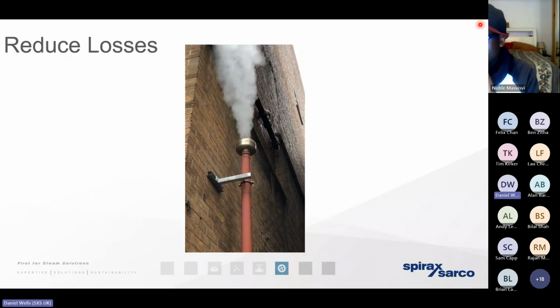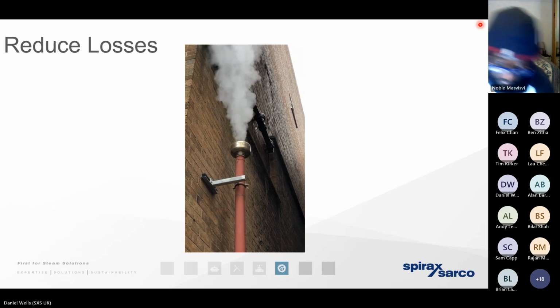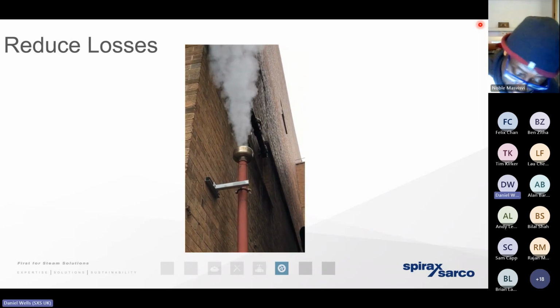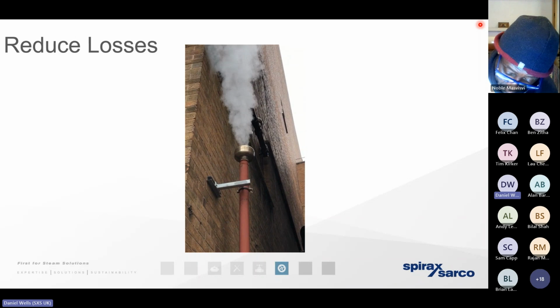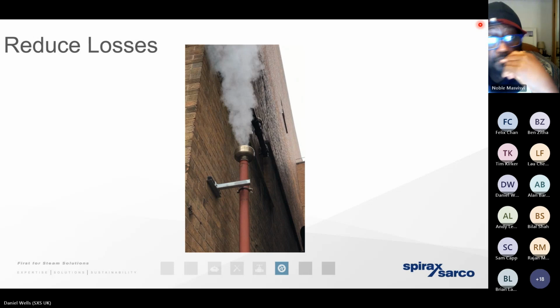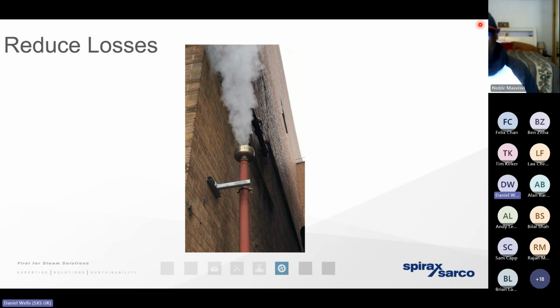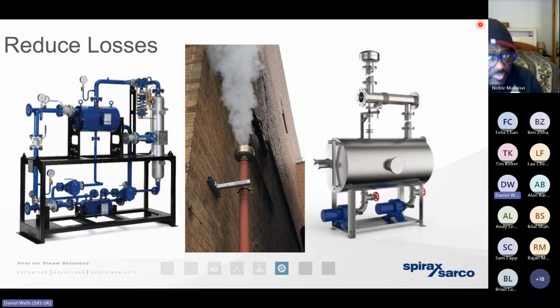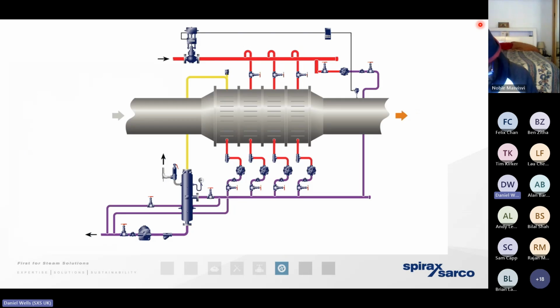So we've spoken about the reasons why we need to vent that steam away. We need to vent it away to protect the infrastructure from damage. But if we know the mass of condensate that is depressurizing and expanding, if we know the pressure drop, then we know the mass of steam, we know the volume of steam, we know the energy content of that steam. We can engineer different solutions to allow that expansion to vent away, but to help us identify ways in which we can recover that energy and put it back into another process. So that could be what we call an in-step process.